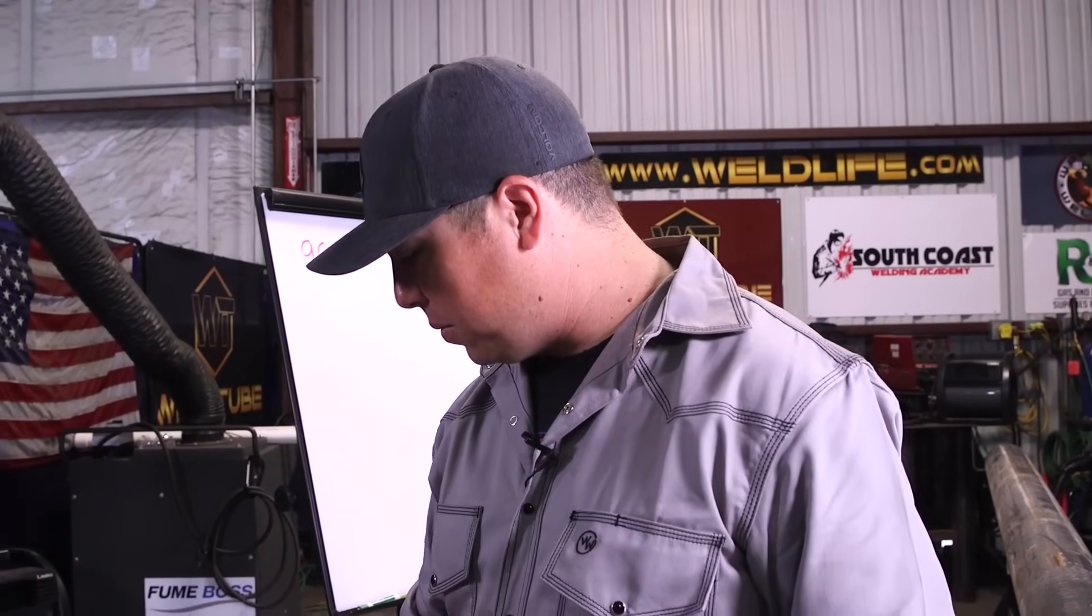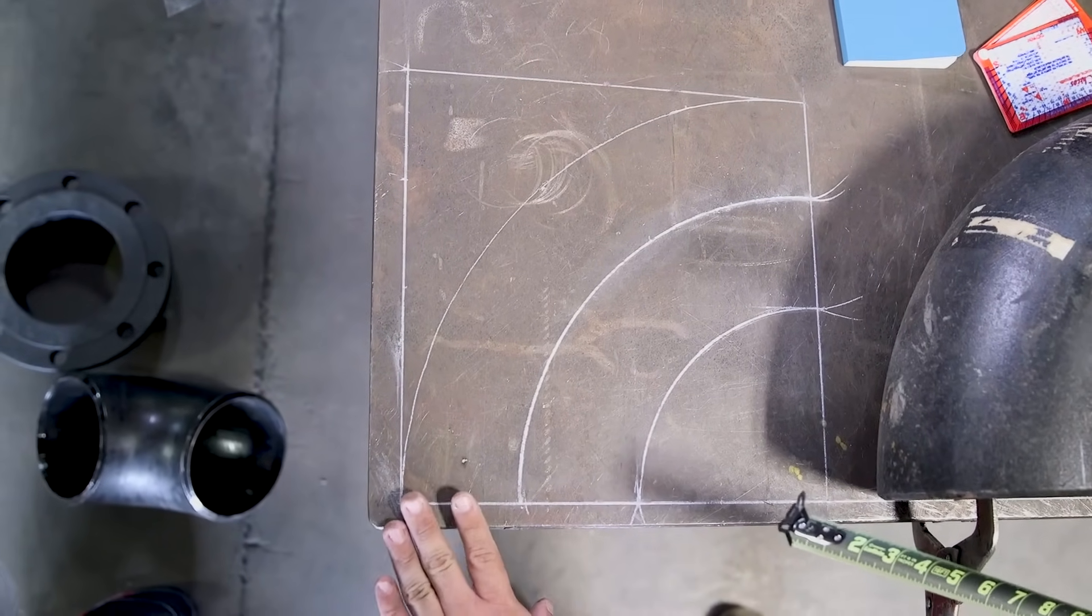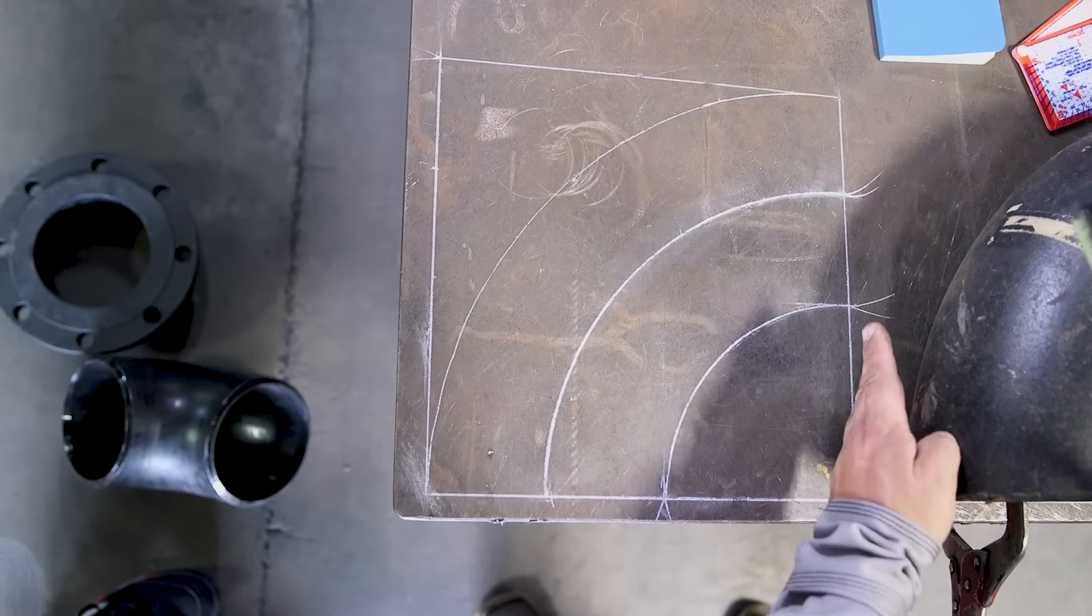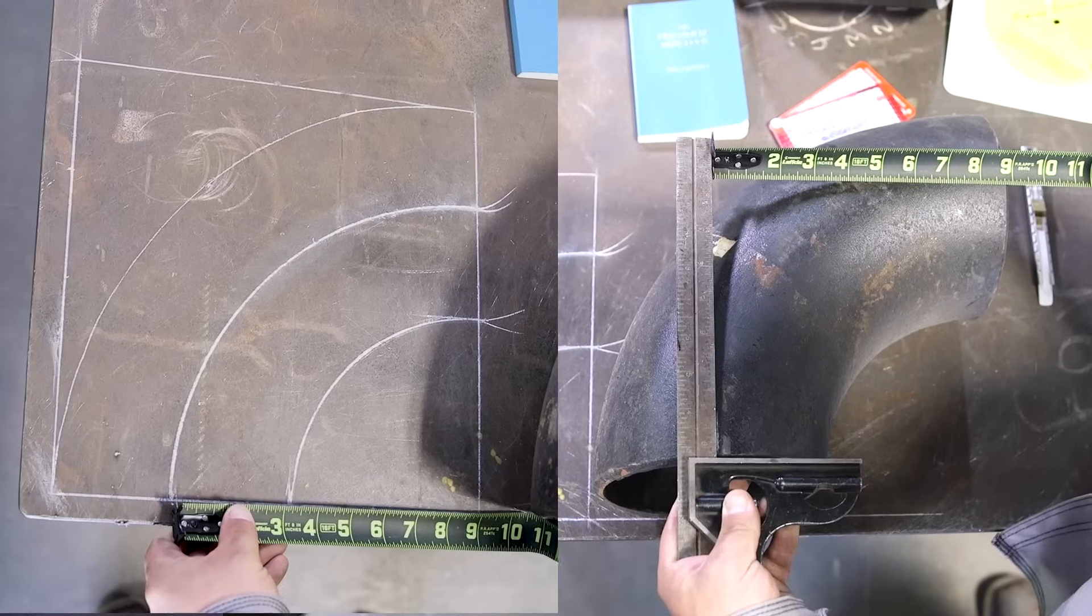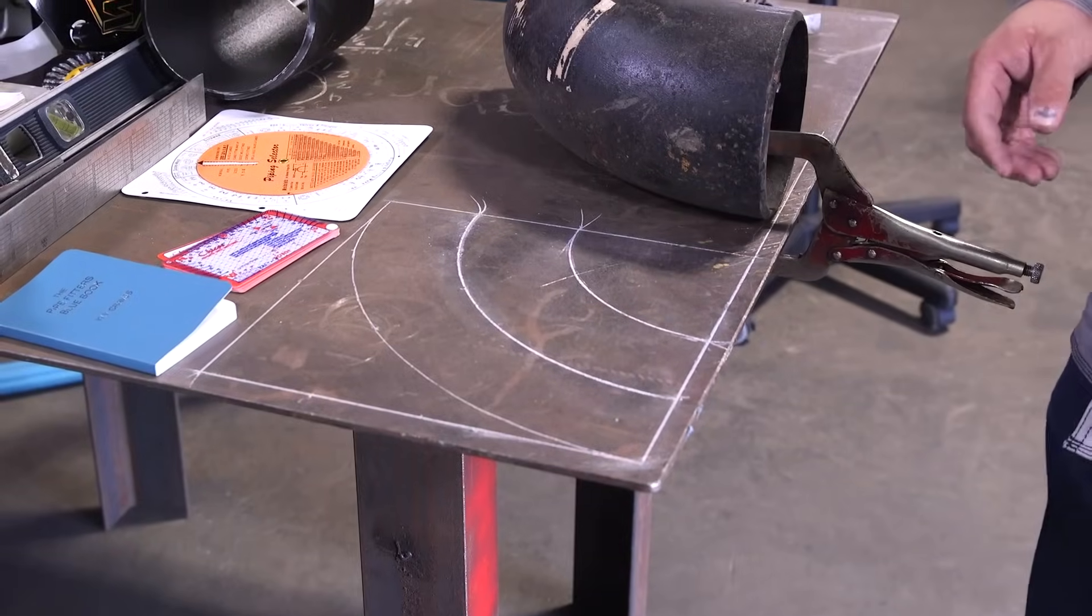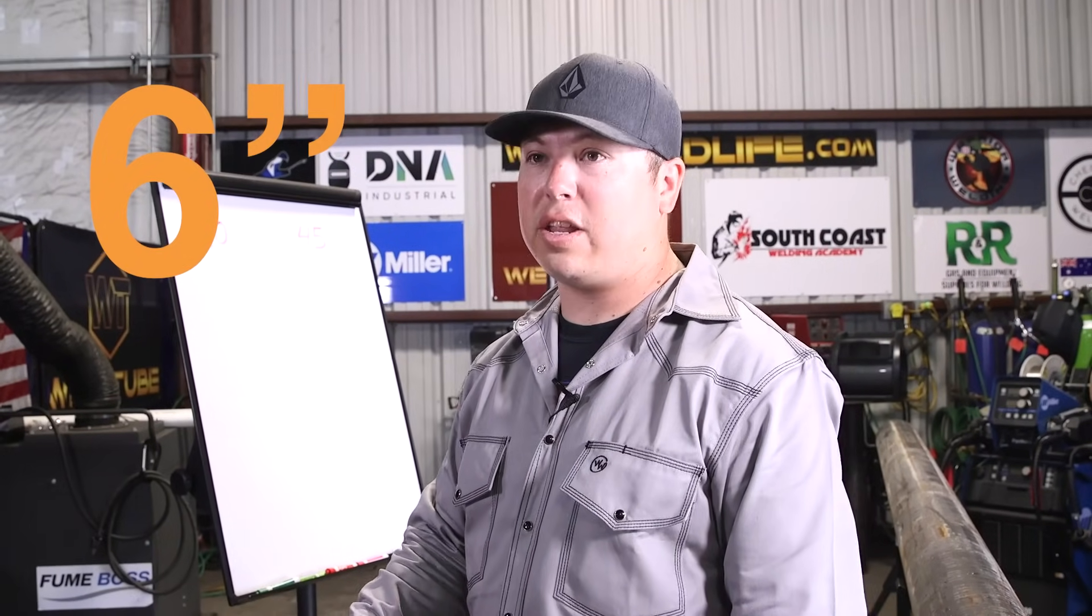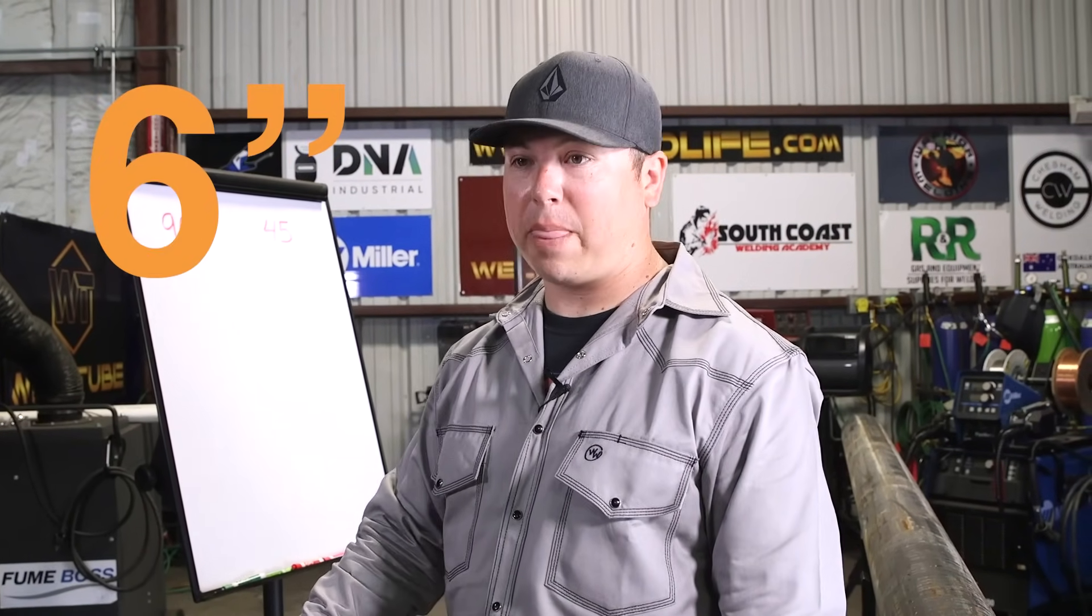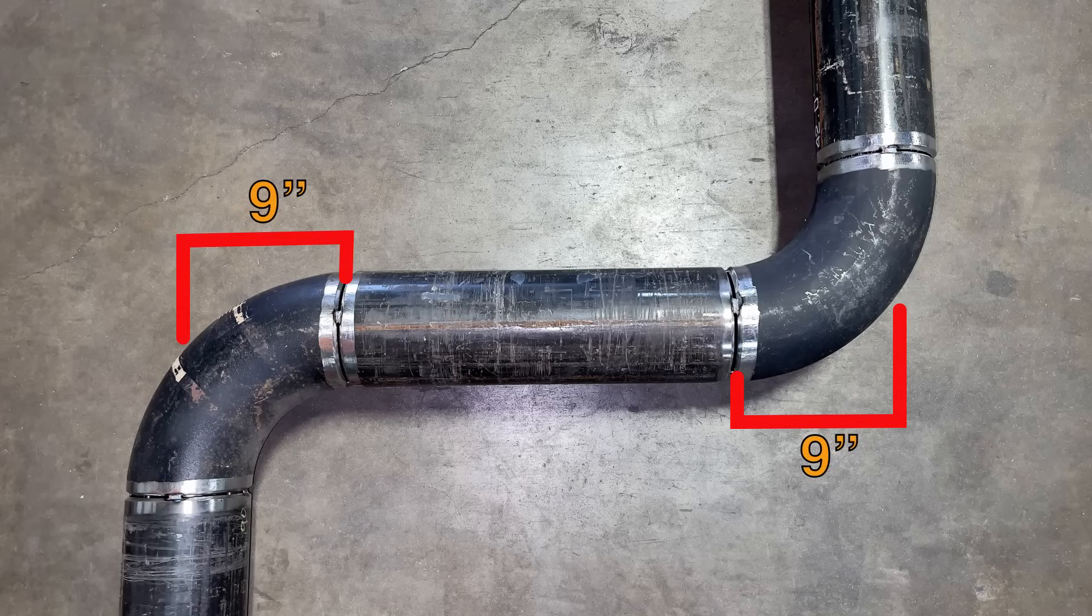So our actual takeoff is going to be from the end of pipe to the center of the 90. As you can see here guys, I've drawn this 90 out onto the table. And if we measure from this end to center here, we are going to get 9 inches. And a common way to do this also is you actually get the nominal pipe size, which would be 6 inches on this case, and then you cut that in half and you add those two numbers together. So 6 inch, cut that in half, we got 3. Add those two together and now we have 9 inches. And that is our total takeoff from end to center of pipe.